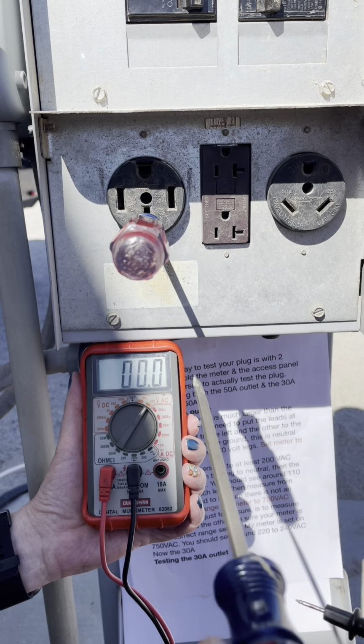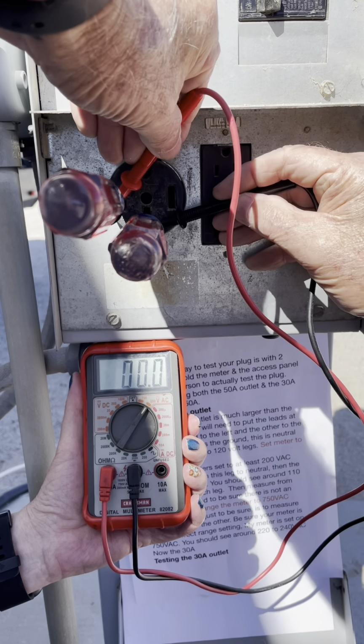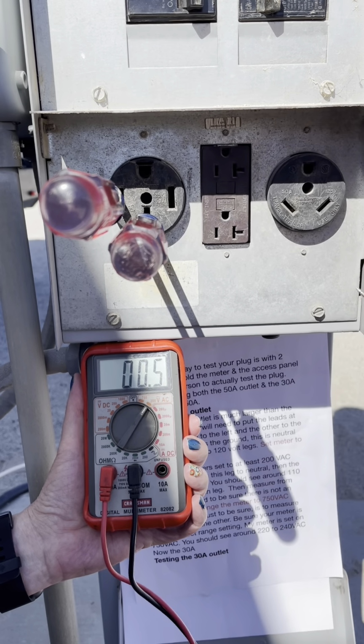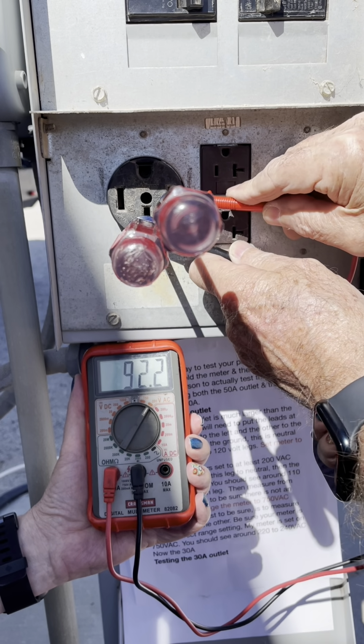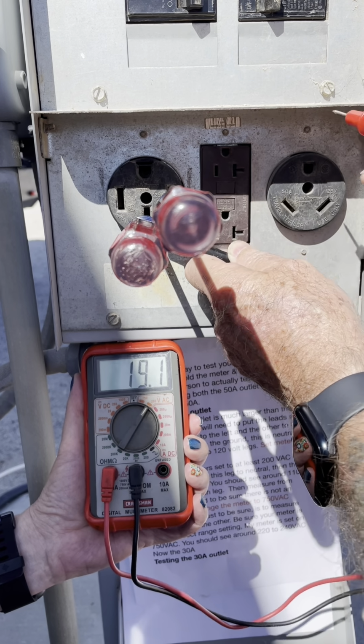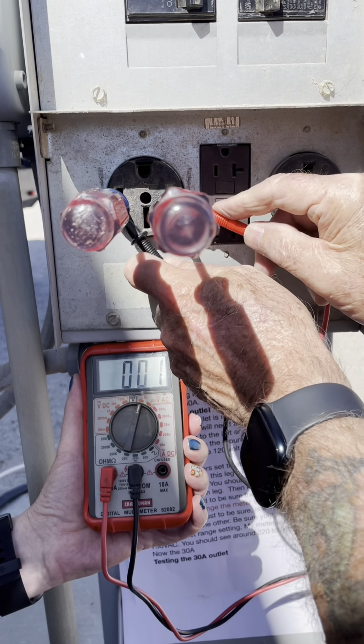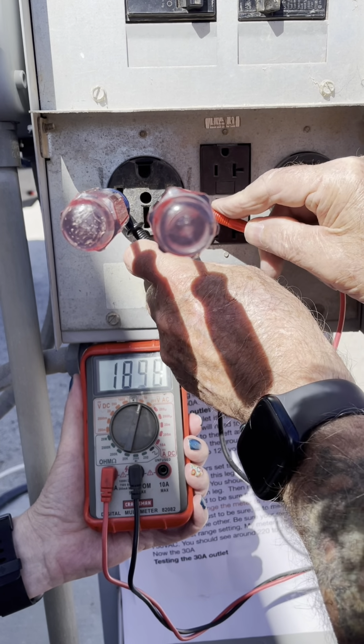First thing we want to do is measure from each leg to neutral. And we should see somewhere around 120 volts. And we're going to measure from the other leg to neutral. Again, 120 volts. We also want to confirm that we don't have an open ground, and we will test from a leg to ground. The last test we want to make is from leg to leg. This is kind of a double check to make sure everything's working correctly. Change your meter to 750 volts and measure from leg to leg. And that should give you around 240 volts. So that's the 50 amp outlet.